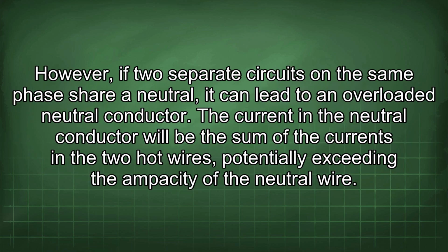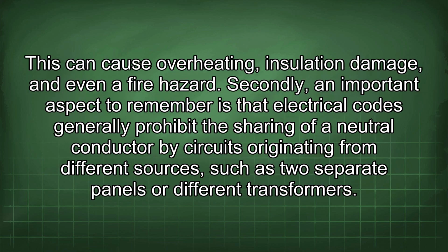However, if two separate circuits in the same phase share a neutral, it can lead to an overloaded neutral conductor. The current in the neutral conductor will be the sum of the currents in the two hot wires, potentially exceeding the ampacity of the neutral wire. This can cause overheating, insulation damage, and even a fire hazard.